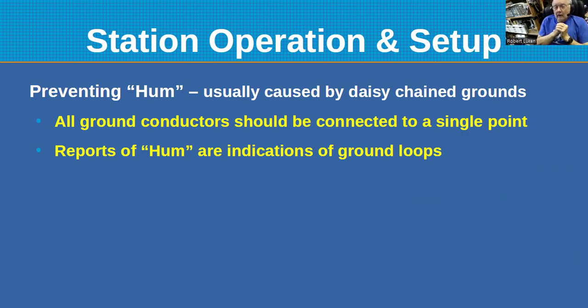You want to have a connection from each device to a single ground, preferably some sort of copper plate or copper bar where everything can be tied, with very low impedance. That should be connected to an external ground.